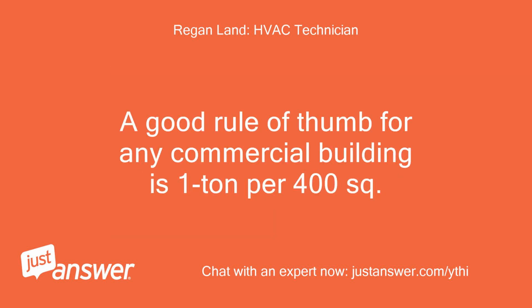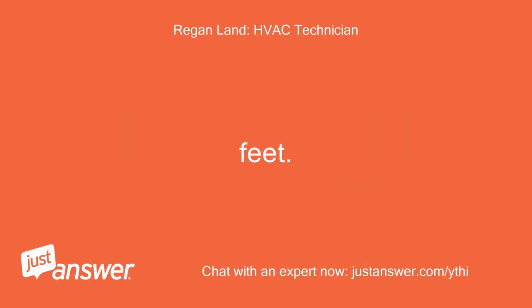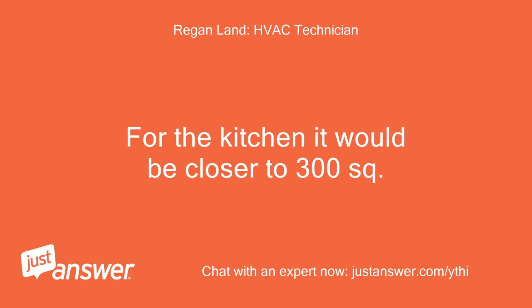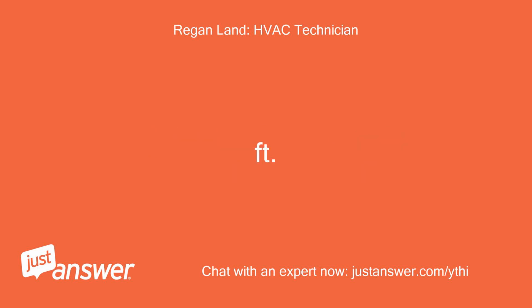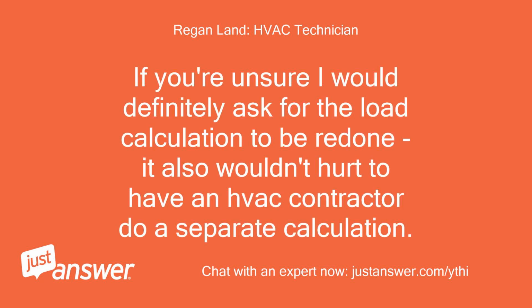A good rule of thumb for any commercial building is 1 ton per 400 square feet. For the kitchen it would be closer to 300 square feet per ton. If you're unsure, I would definitely ask for the load calculation to be redone. It also wouldn't hurt to have an HVAC contractor do a separate calculation.